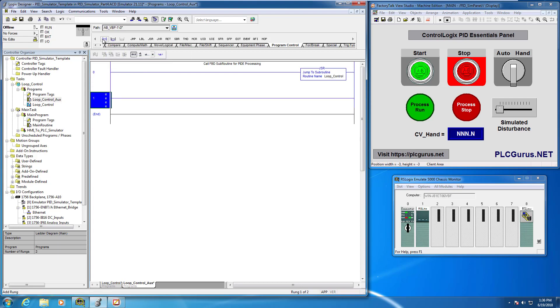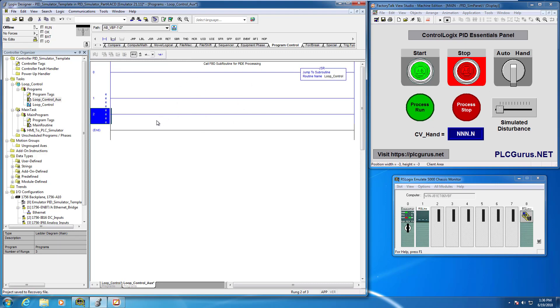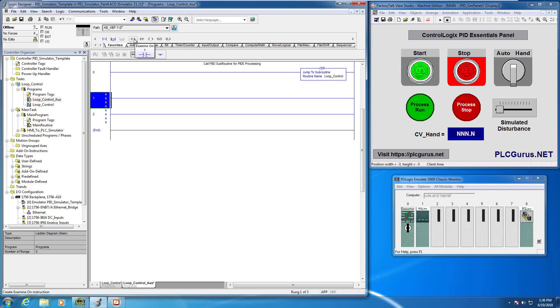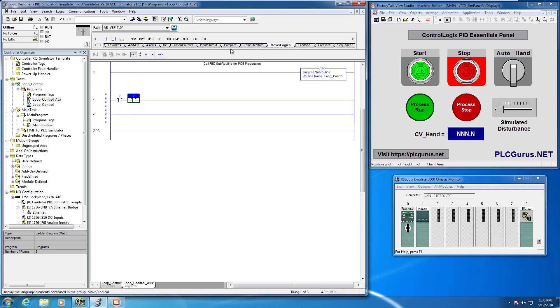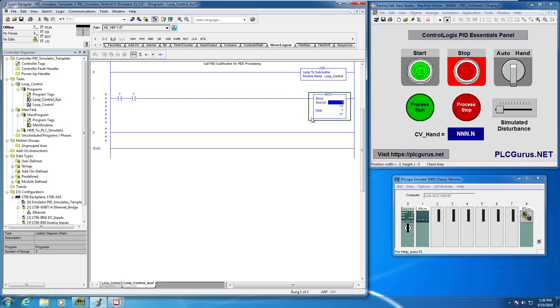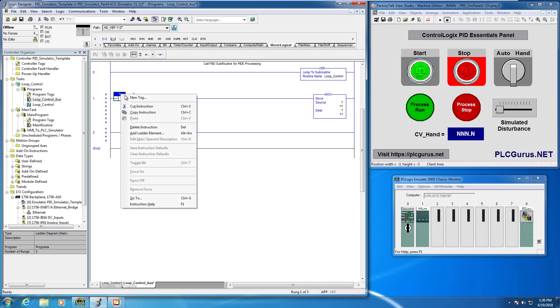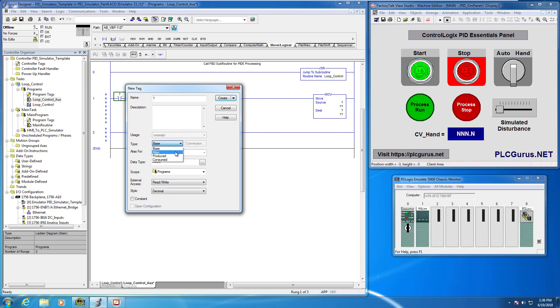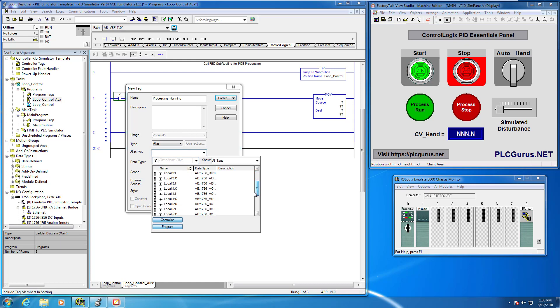Next I want to start populating some of this I/O so that the simulation panel can start doing something in our program. I'll add two XICs and a MOVE instruction. For the first one I'm going to create a new tag called 'process running' — this will be an alias type for the output pilot light, specifically local 5 output data 0. I want to change the scope to controller scope since I'll want access to these tags across multiple tasks and programs.